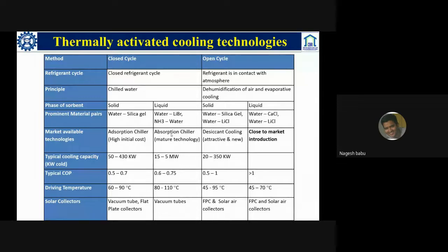with one single system. The open cycle, if you are looking at, we can meet up to a maximum of 350 kilowatts. So these are the systems that are typically used for apartment complexes or for large multi-specialty hospitals, something like that. We have typical COPs of open cycle around 1. And if you are going for liquid type systems, we also have greater than 1. Liquid systems also have another advantage: they have low regeneration temperatures of around 45 to 70 degrees centigrade. So we can use evacuated tube collectors or flat plate collectors for solar heat.